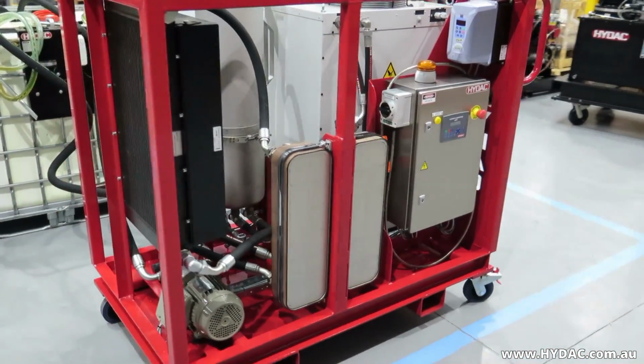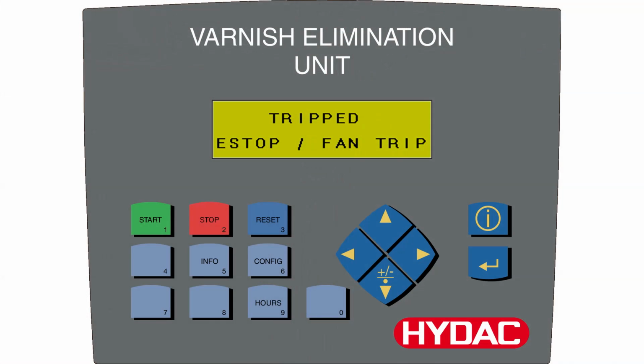Here are some of the alarms or trips that you may encounter. E-stop/fan trip: emergency stop activation. Inlet pressure: a negative pressure is detected in the pressure line. This is a cavitation warning. OLF filter clog, replace element: the OLF element is 100% clogged. Pre-filter clog, replace element: the pre-filter element is 100% clogged. OLF overpressure: high pressure detected. Wrong phase DIR: the chiller motor is rotating in the wrong direction. In this case, a qualified electrician must verify the phase rotation of the supply power.